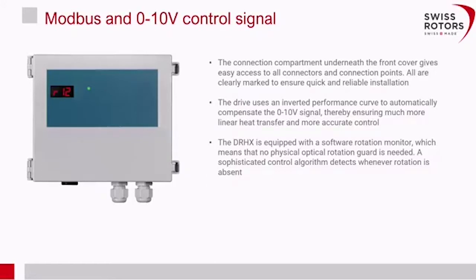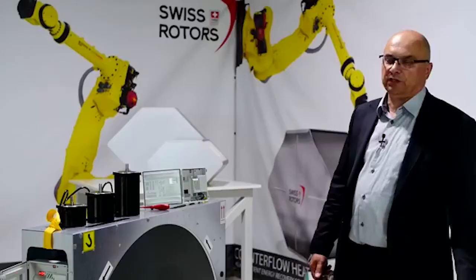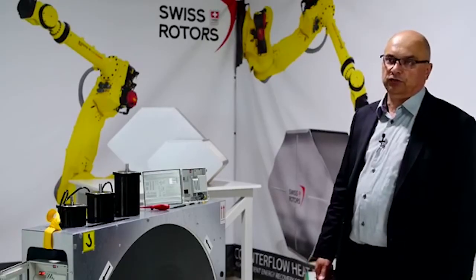And then something about the Modbus. About the controller. The controller could be controlled by the Modbus, so we have a standard RJ12 plug, but the speed of the wheel could also be controlled via 0-10 volt signals, depending on what kind of application you have and what kind of controller of the air handling unit is used.